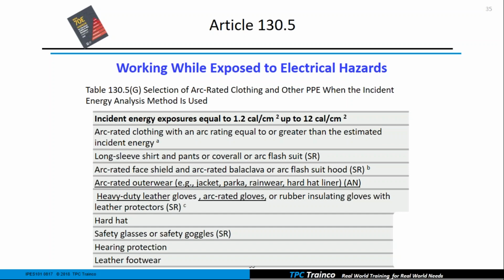So that's a big difference between the incident energy analysis method and the PPE category method, because with the PPE category method, I had to put a flash suit on when I got above 8 calories. Here, the manufacturers are making clothing all the way up to 12, which is nice. So I could have a 12 cal shirt on, 12 cal jeans, put my hard hat and face shield on. I can purchase a hard hat now with a balaclava built right in, get my gloves on, and really, if I'm wearing the shirt and pants throughout the whole day, that's my work uniform. Then I'm just throwing on my hard hat and gloves. So it makes it quite a bit easier for us. But this table will go with method number 1.